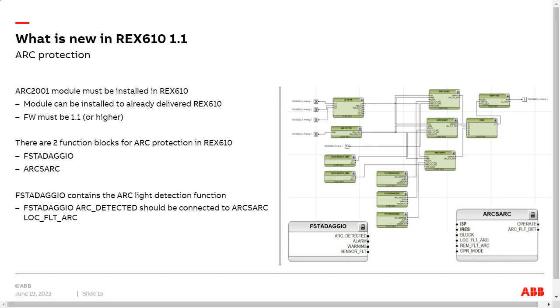That of course depends on the case. Then the warning signal is actually looking at this compensation. For example, if you have compensated the device, but this arc protection function is registering a slow signal change that exceeds the background compensation value, that will indicate that either you have not performed the arc compensation properly, or you have some other thing generating additional light. It's a slow change, not an immediate change of the light, so it might be worth investigating whether you need to do a new calibration, or if something else generates additional light.